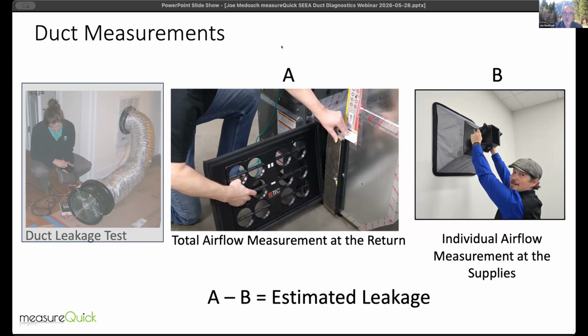It goes fairly quick, and you can get all your measurements and find out what your total flow is. Once I know what the flow is after my return, I can go around and use a simple hood and measure the supplies. And this is an estimated leakage, but if I know the airflow that's coming out of my unit and I figure out what my supplies are, there's an indirect concept now.